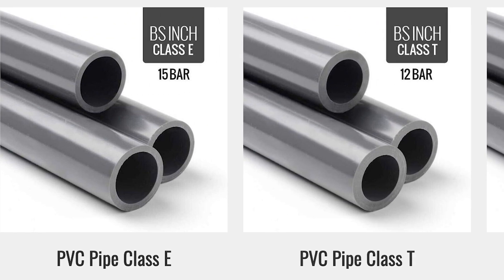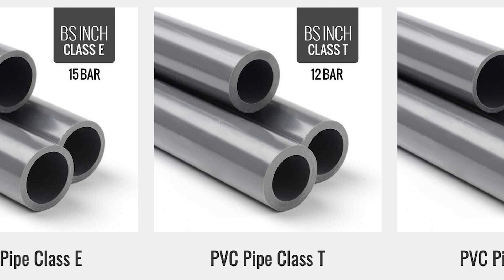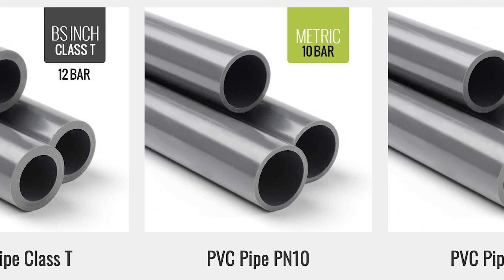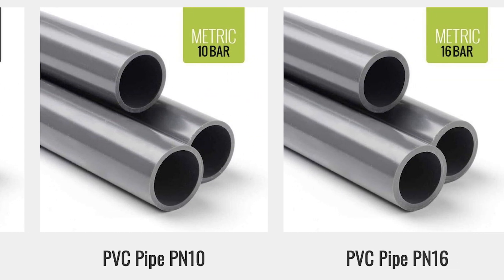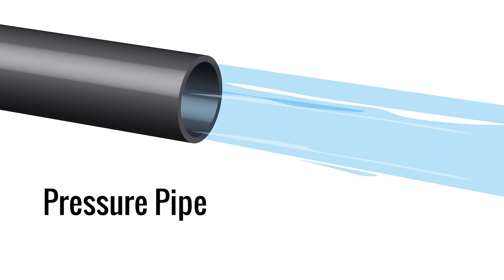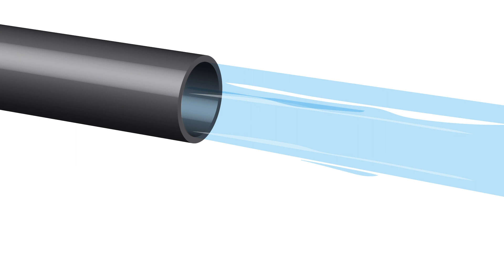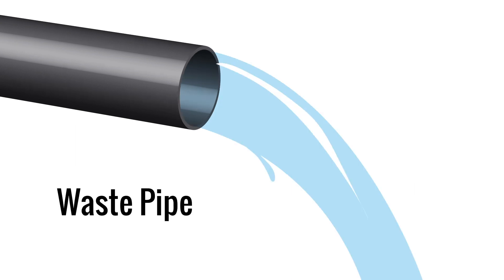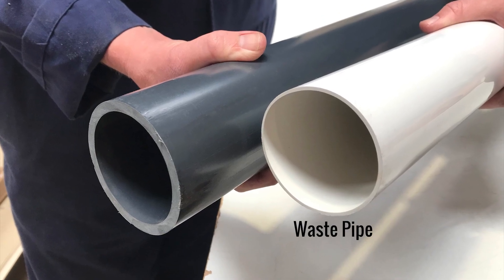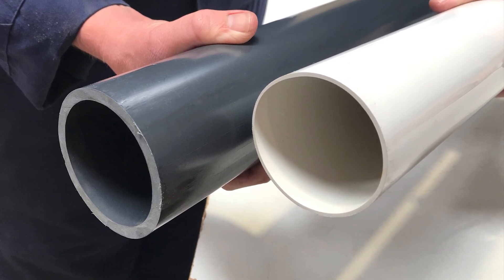Hello and welcome. Today I'm going to be talking you through the way that UPVC and ABS pressure pipe is rated and classed according to its pressure handling capabilities. All pressure pipe is designed to convey fluids or media under higher pressure; this differs from waste or drainage pipe that is designed to convey media under gravity. The way in which pressure pipe deals with the elevated pressure is by way of an increased wall thickness.